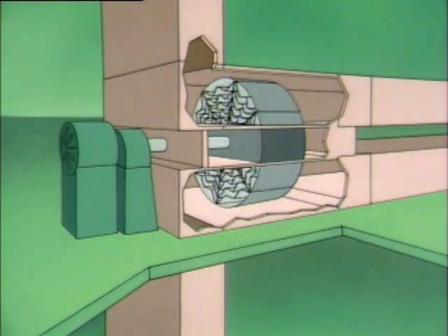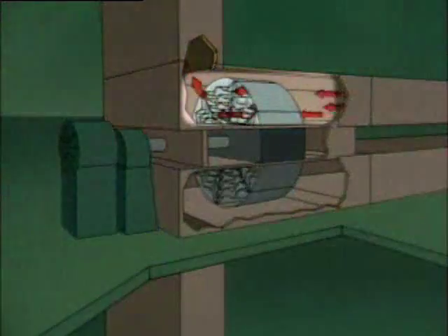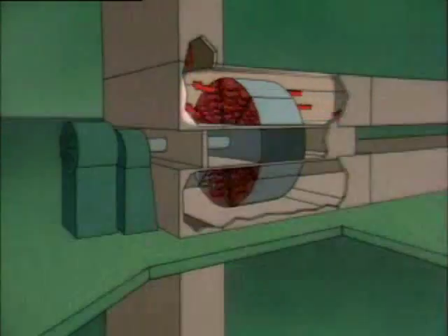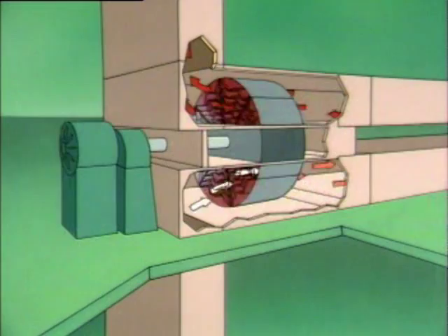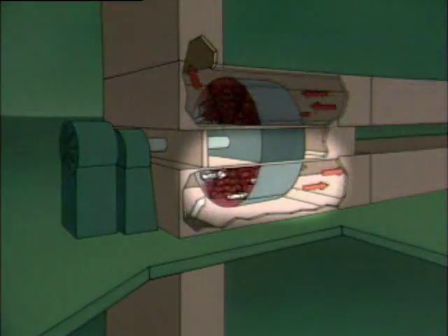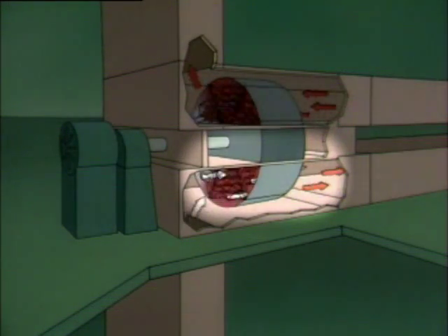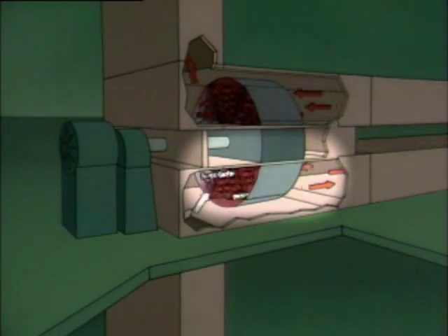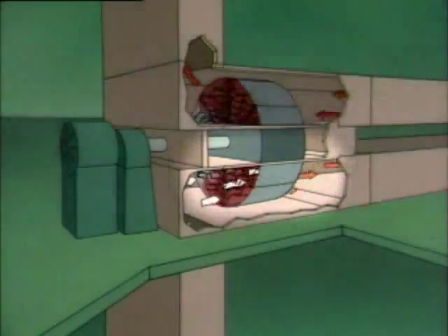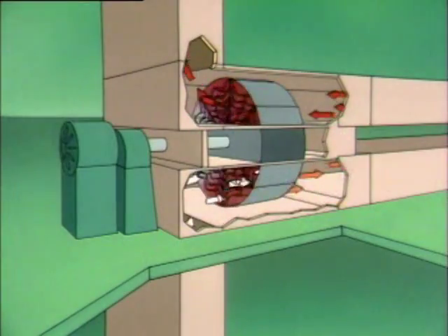The heating surfaces rotate through the hot combustion gases. So, in this section, the heating surfaces are warmed by the hot gases. Then, the rotating heating surfaces transfer heat to the cooler air flowing to the boiler. The warmed air is sent to the boiler's combustion area.